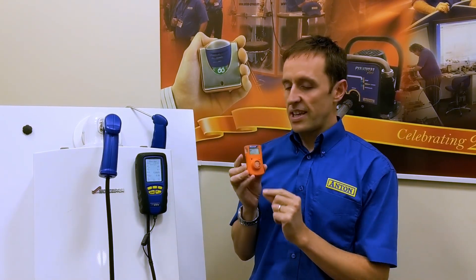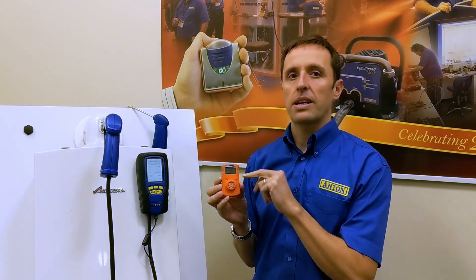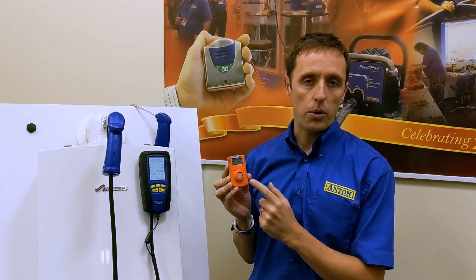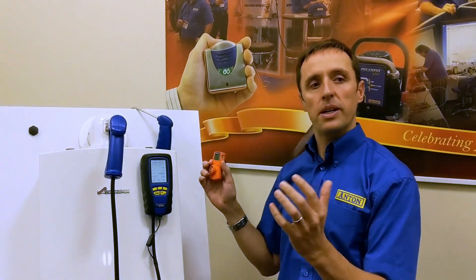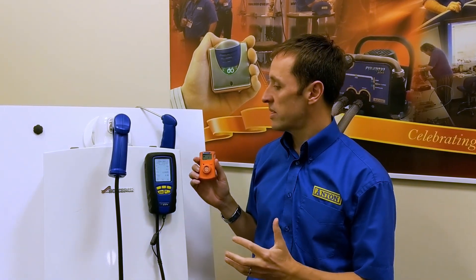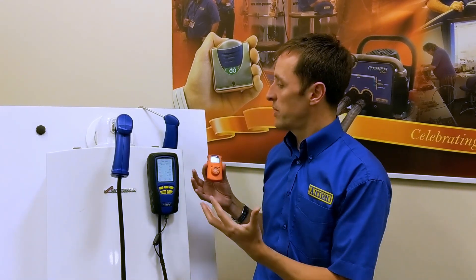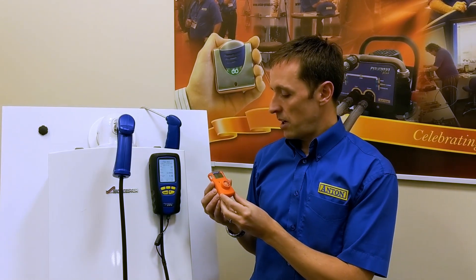The benefit of one of these things is it will tell you if there's carbon monoxide there at a low level. You'll never be exposed to a dangerous level because the first-level alarm will go at 30 parts per million. So if there's a high concentration around the boiler as you walk closer to it or further away, it's going to go off long before you get to the very concentrated carbon monoxide around the appliance. Or if you start it up and it starts producing carbon monoxide spilling back into the room, it's going to warn you as it starts to accumulate.